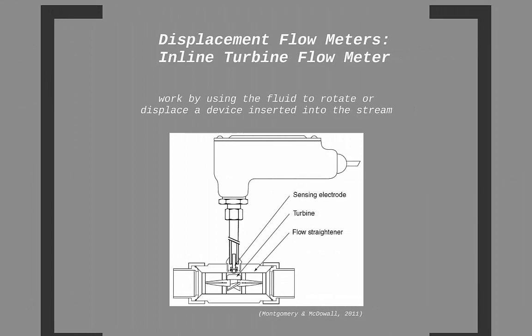There are also flow sensors which are classified as displacement flow sensors. They are defined in the Montgomery and McDowell text as those sensors that work by using the fluid to rotate or displace a device inserted into the stream. An inline turbine flow sensor has a turbine placed in the flow stream. The faster the flow, the faster it spins. Its revolutions are counted via a variety of methods, and those readings indicate the velocity and/or volumetric flow rate of the fluid stream.